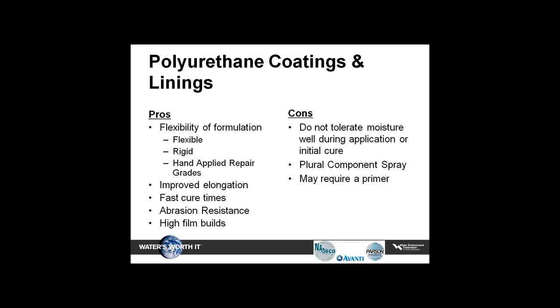Polyurethane coatings and linings: the pros are flexibility — very flexible with 50-60% elongation — along with rigidity in their film. They can be hand applied with certain technology, have very good elongation, fast cure times, and very good abrasion resistance — up to a quarter inch or high film build. The cons are they do not tolerate moisture at all during application, so they cannot go over surface saturated conditions. They must be sprayed through a plural-component pump and require a primer.